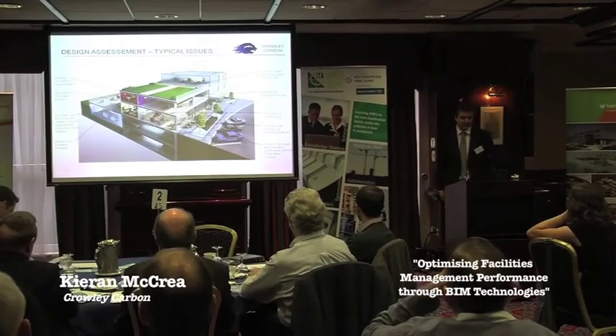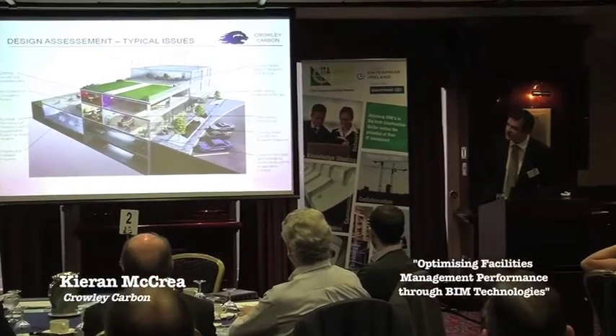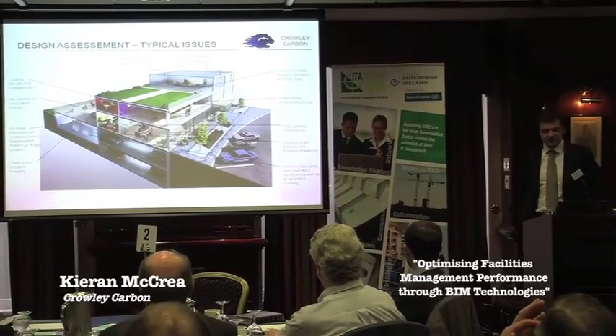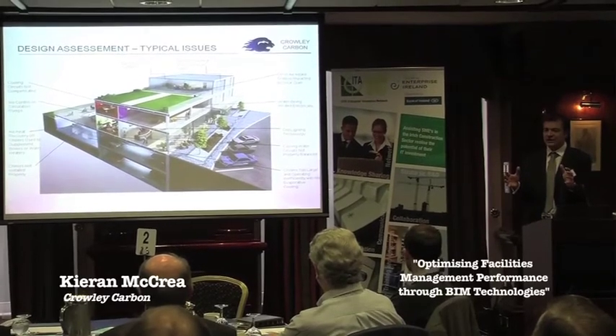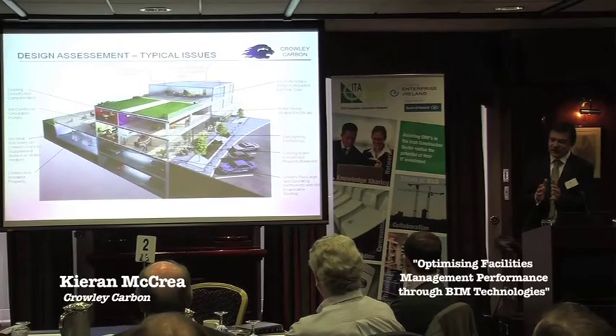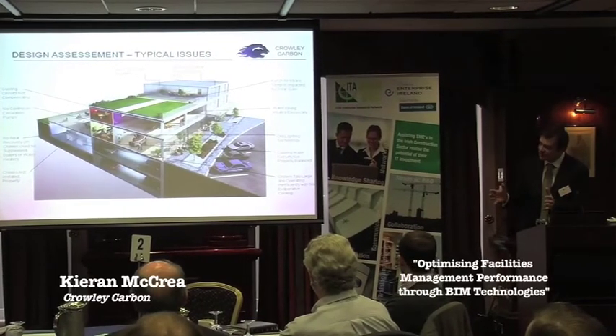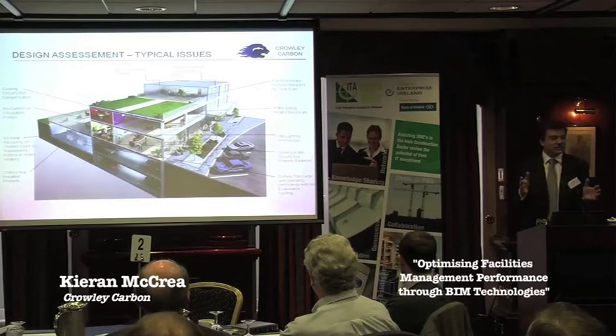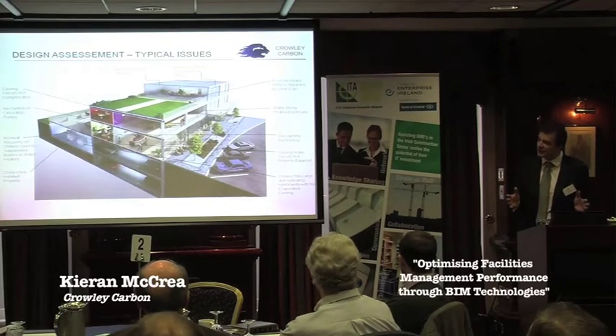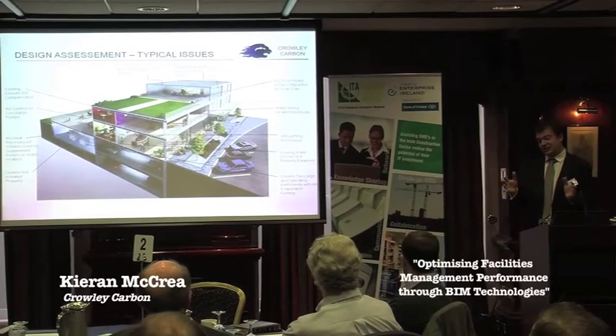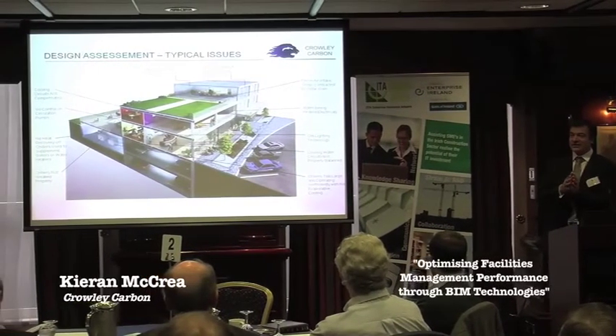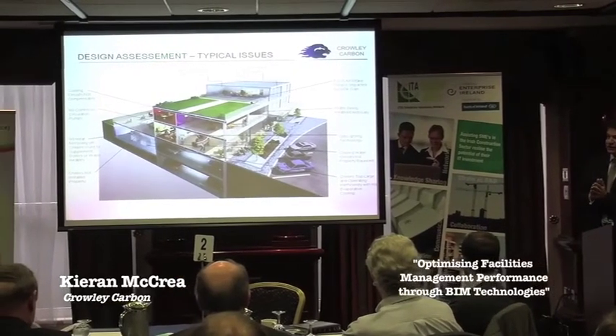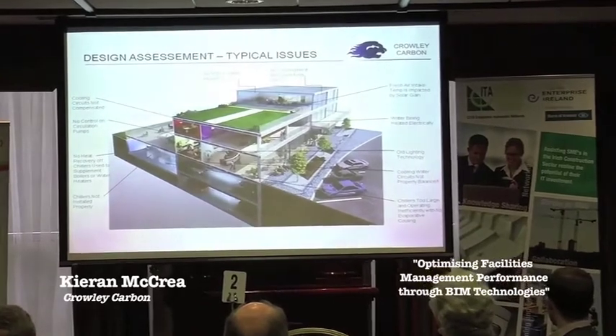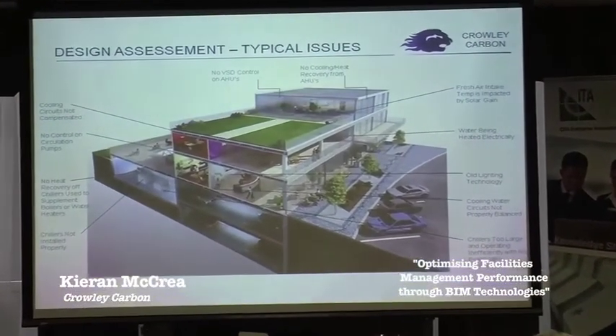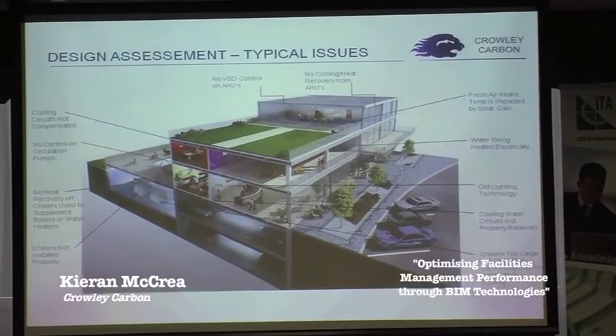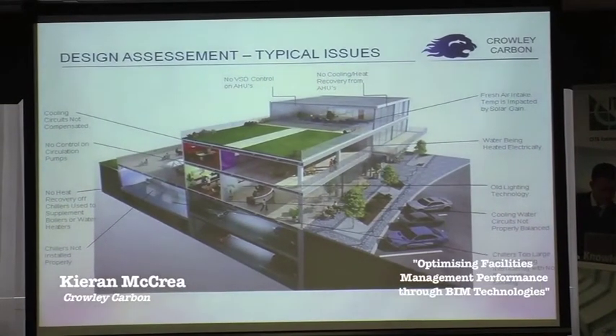Another example of what we look at in terms of design is the chiller. Often when a building is designed, the chiller is specified, and then for a margin of error it's increased in size by about 30%. When you go to buy a chiller that's exactly the right size, you might find there isn't one available, so you buy one a bit bigger, then find a deal on one bigger again, and suddenly you end up with a chiller nearly twice as big as needed. That's great value for money, but it uses twice the power it needs on an ongoing basis. That's the kind of thing we look at, and we can remedy it.